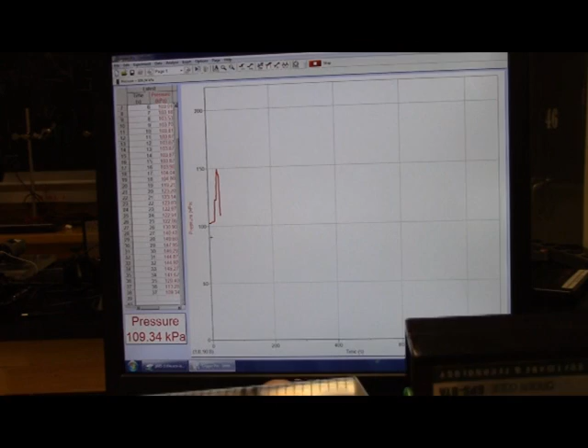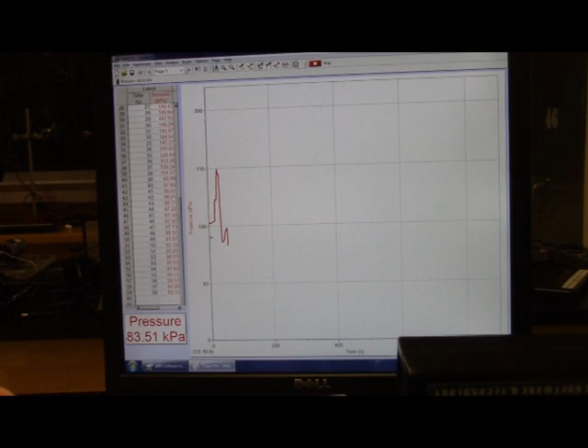If I let it release again, go back - here I'm going all the way out to 15 now. You can see the pressure has dropped below where you started initially. You may have to hold it if it's not too stiff, then this plunger will move on its own. So when you're doing your measurements, if you want 15, you've got to make sure it's held there.